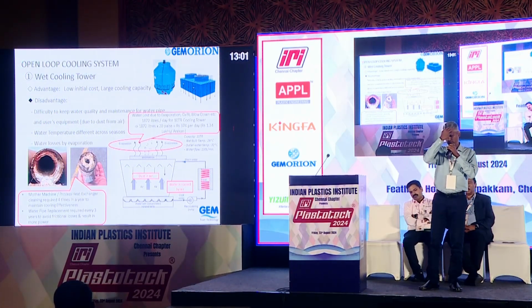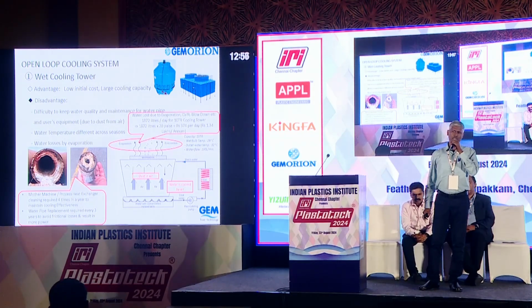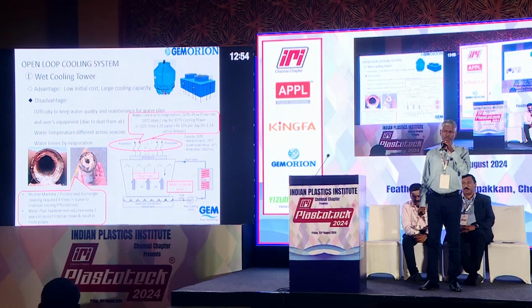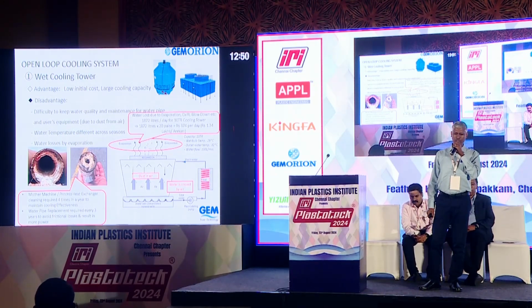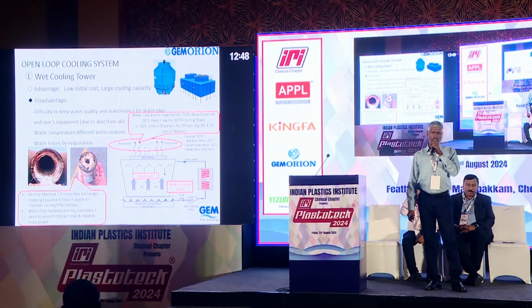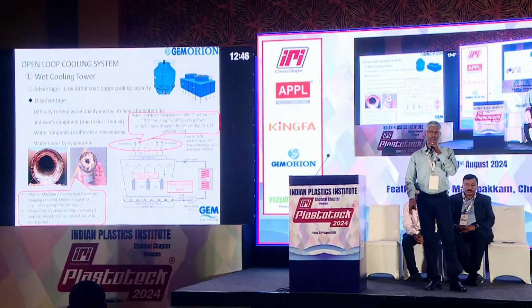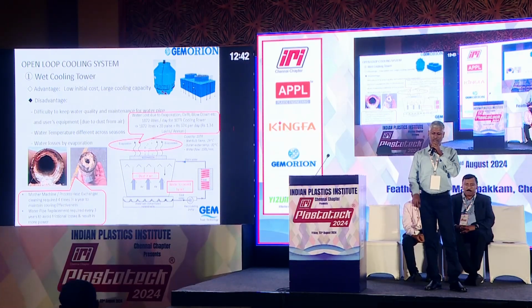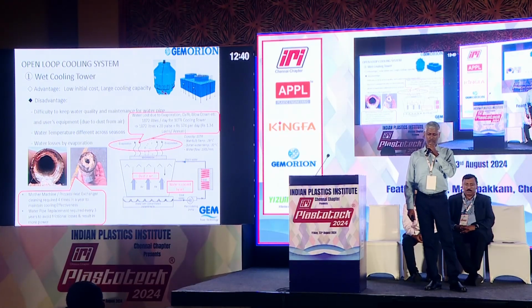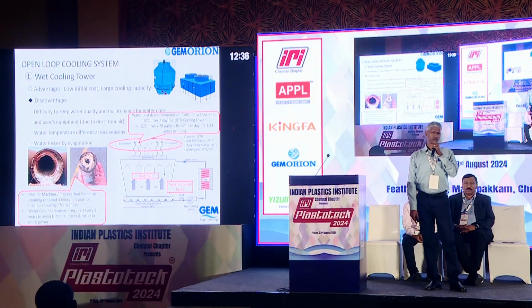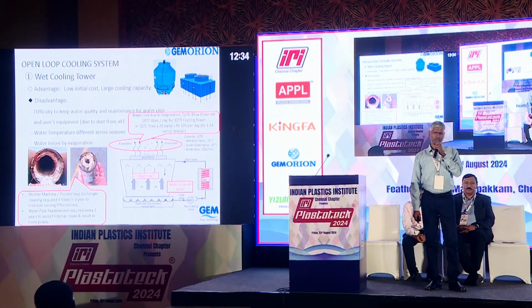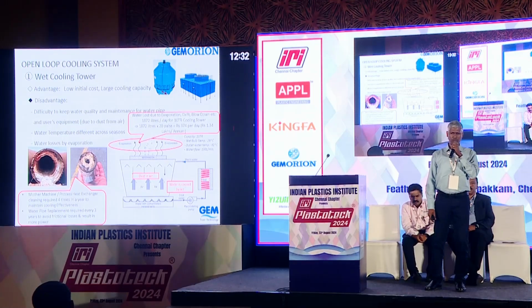Now going into the cooling system, as I said, if we want to achieve a temperature above wet bulb, then this simple cooling tower is more than sufficient, and it is the most economical one. Very simple investment, easy to operate, just connect with your machine and you'll be getting cold water. But the problem is the water will be evaporating, and even in Chennai or many places in South India, people buy treated RO water and use it in the cooling tower to avoid this kind of scaling problem.